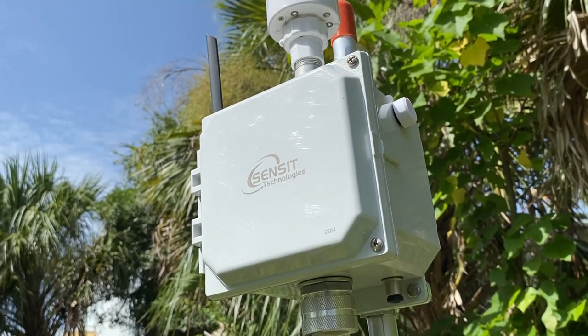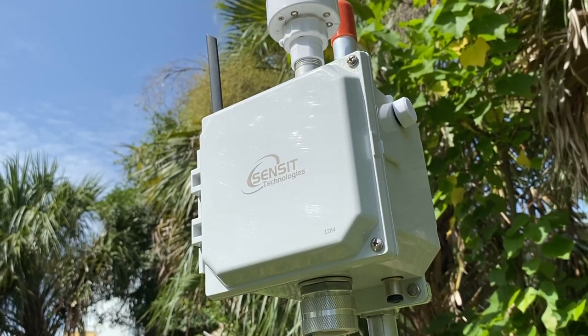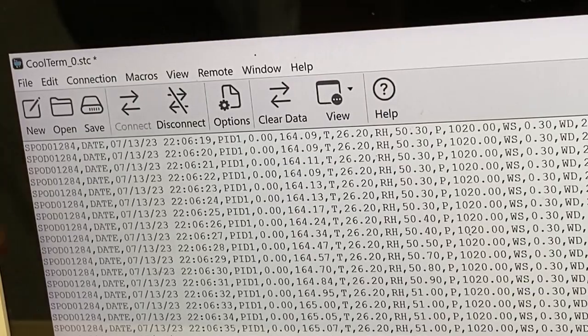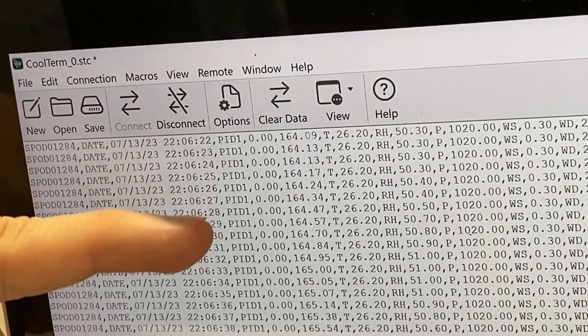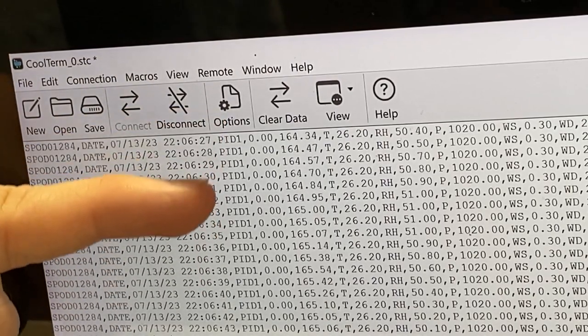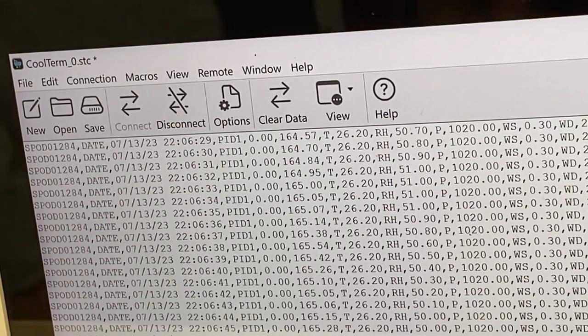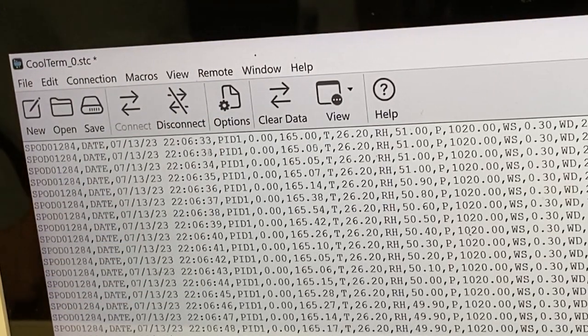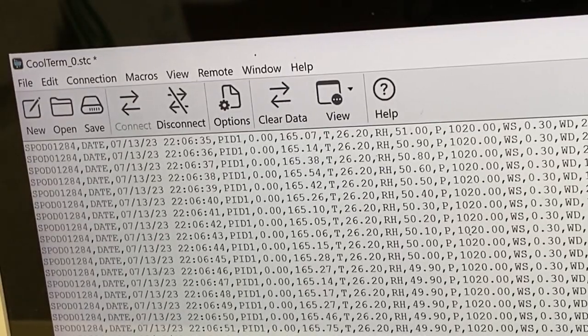At this point, the PID has been exposed to fresh ambient air for at least three minutes. Check the readings on your computer. The readings next to PID 1 is the number you are observing. It may take several minutes more if you are in a location with a high volatile organic compound background.